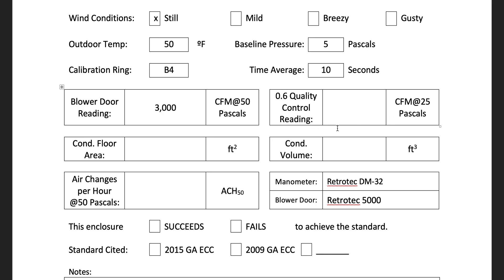This is a special field: the 0.6 quality control reading. What that means is we want to take your 50 pascals and cut it in half. So instead of going to 50 pascals, reset your manometer and run the fan to 25 pascals. If you're using cruise control in Energy Conservatory or Minneapolis equipment, or the AT function where you set it to a pressure, this will calculate it for you automatically. Make sure you're not in AT-50 mode while you're trying to drive to 25 pascals, because that would be problematic.